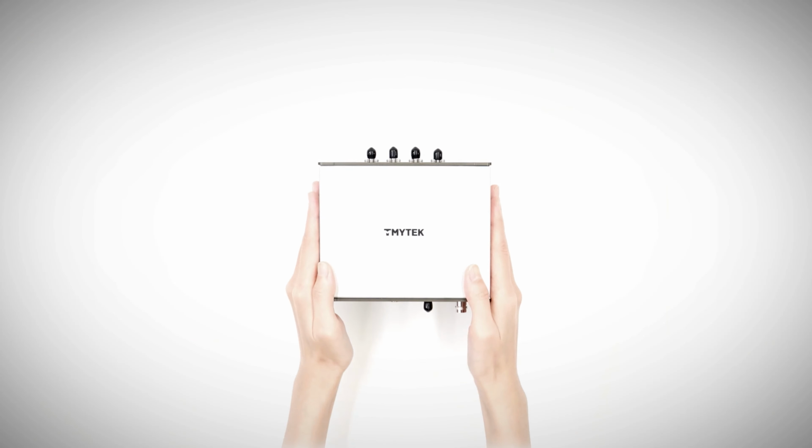LED indicators. When powered on, the lock LED should turn red. The CH1 and CH2 states are determined by the TMYTEK Lab app. White means it is transmitting a 10 MHz source to sync other device clocks. For the 100 MHz clock LED, white equals transmit, blue equals receive.